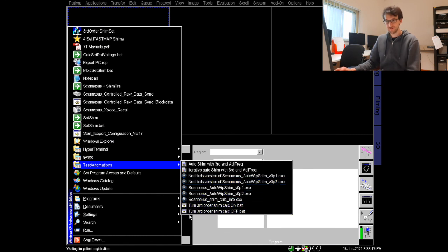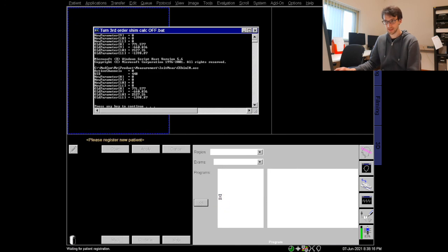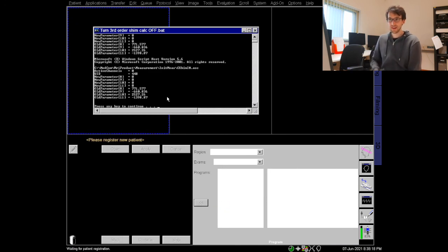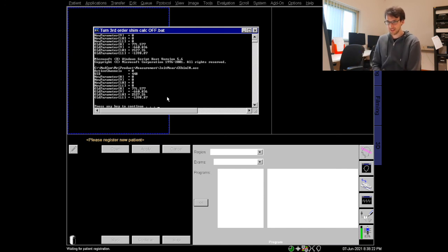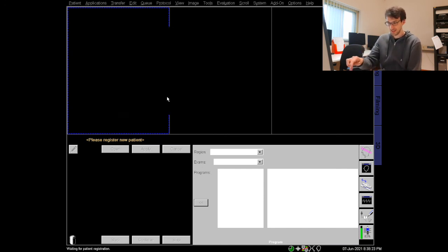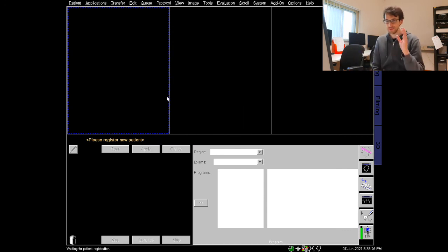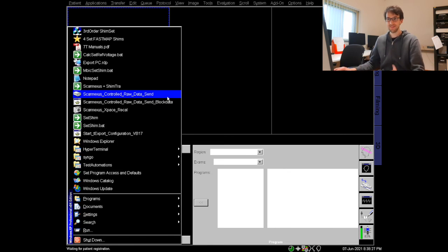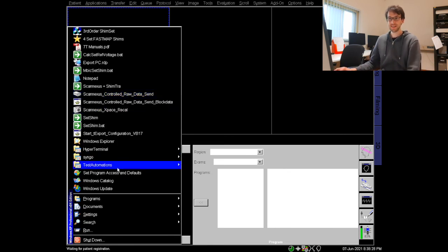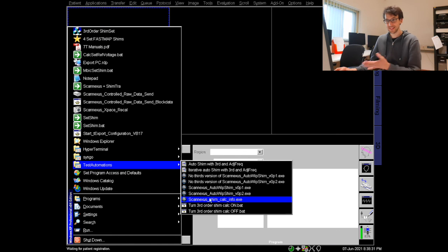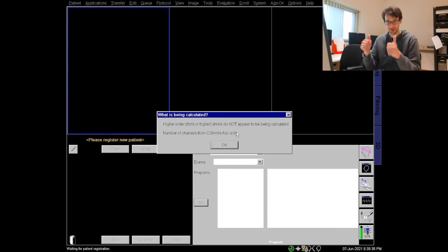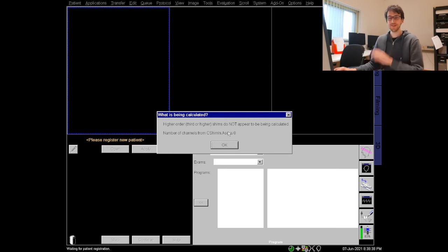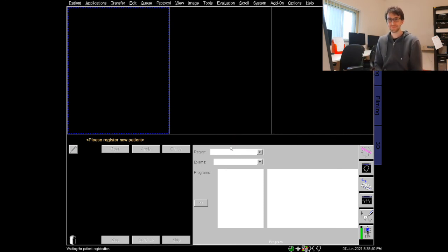It's finished by pressing any key and hitting any key. To be really sure I again go to my test automations and use the Scannexus shim calc info.exe which now gives me the zero. This is all good and only when this is zero I can leave the scanner. So thank you for watching.